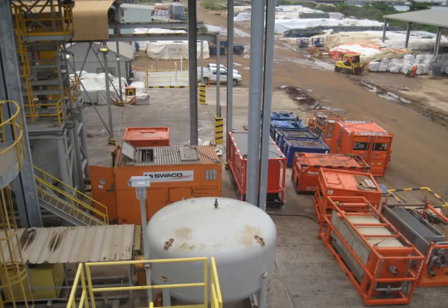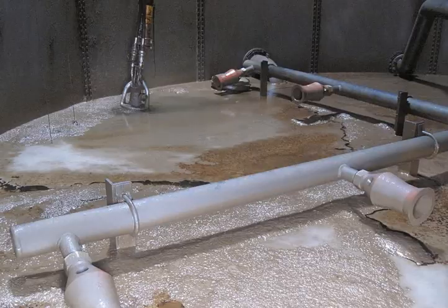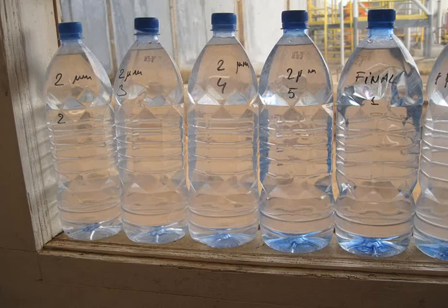The plan agreed with Chevron was to set up a yard test to better understand how this innovative technology can be implemented offshore. The picture shows the actual equipment layout for the yard test. The water used for the test was the wash water from tank cleaning operations. The test results confirmed that using this method, slop water can indeed be treated for offshore disposal. Lab testing results confirmed oil content as low as 3 ppm — 10 times better than required.